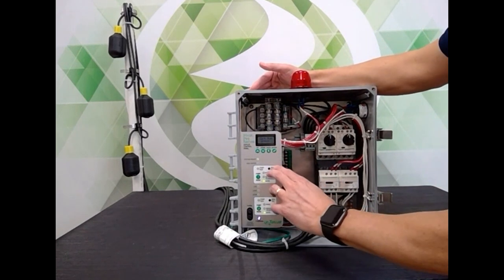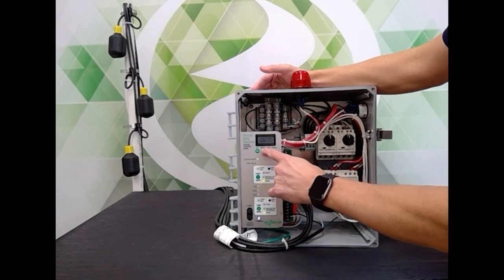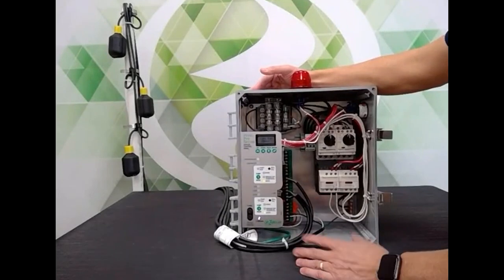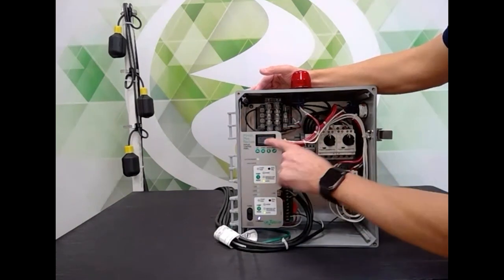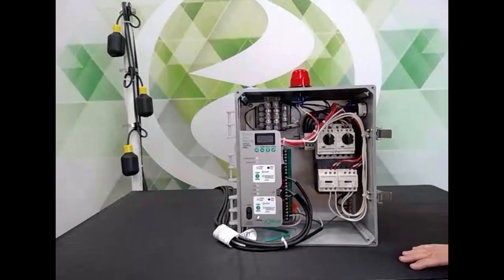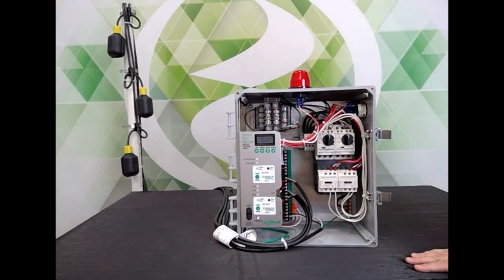All of these kinds of timers and settings are very changeable and easy. Let's say I have a pump that typically runs for about 10 minutes — I want to change my continuous run from 20 to 12 minutes because I want to know if it goes an extra two minutes. I hold back and enter together and get a little asterisk next to continuous run, showing I can edit. I hit my down arrow until I get to 12, then hit enter. Now my continuous run timer will go off after a pump runs continuously for 12 minutes. These settings usually only have to be done once during startup.